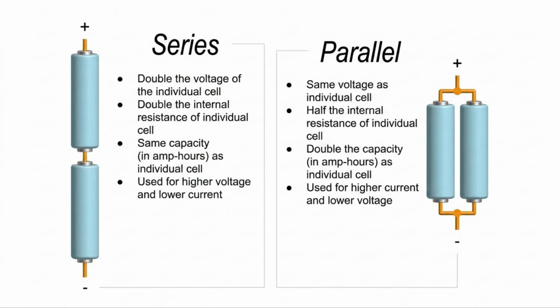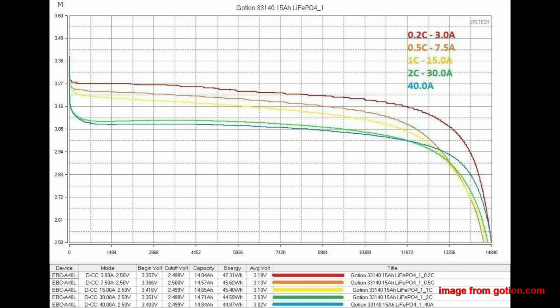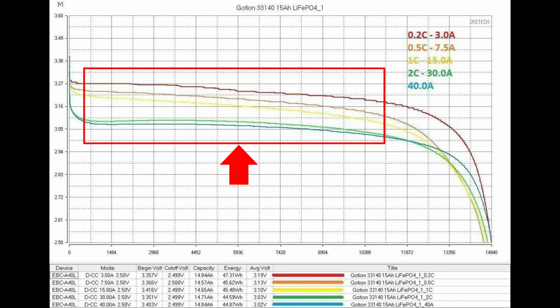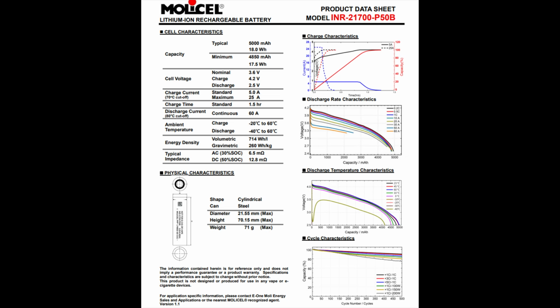Now, in designing a battery layout, you have a couple of things to consider depending on the type of cells used. Each cell has a voltage range from peak voltage at full charge to a minimum voltage that will be at a lower state of charge or under extreme load. The nominal voltage is typically in the middle of that range, where the battery will stay during the majority of the charging and discharging process.